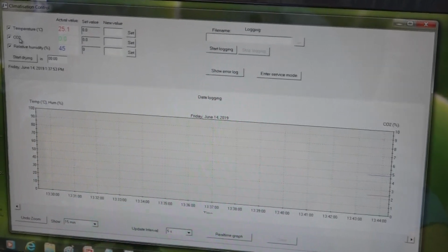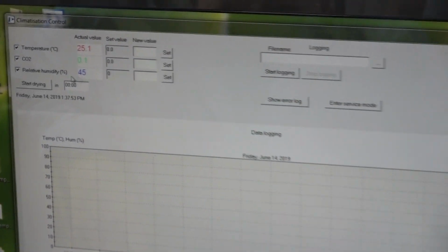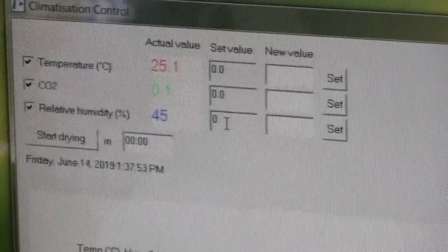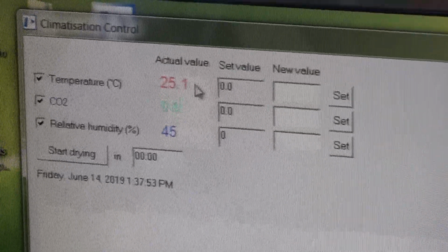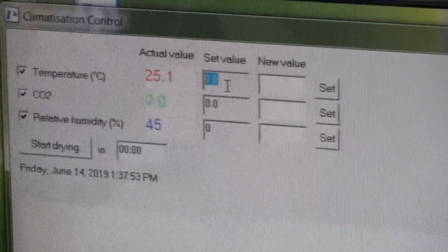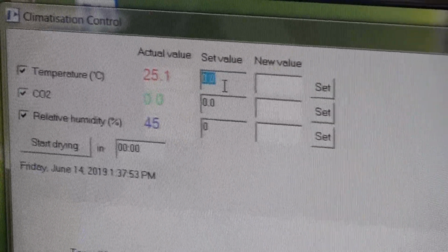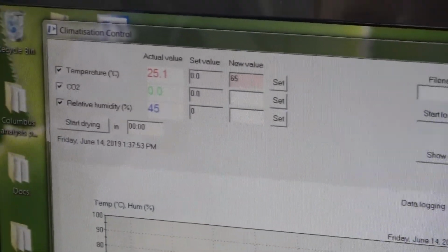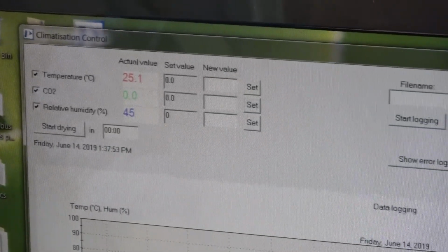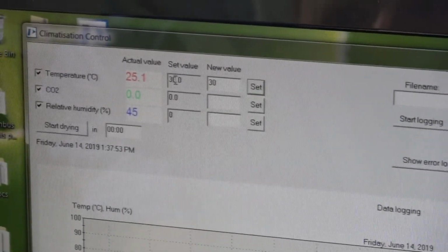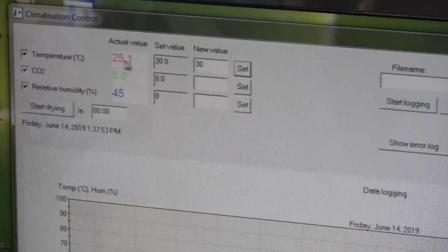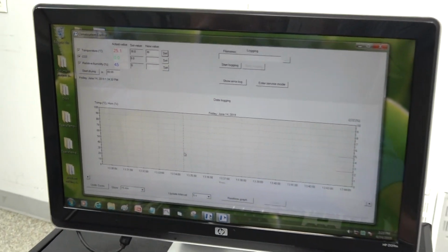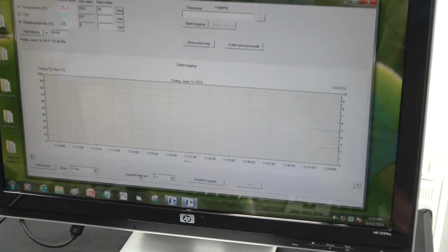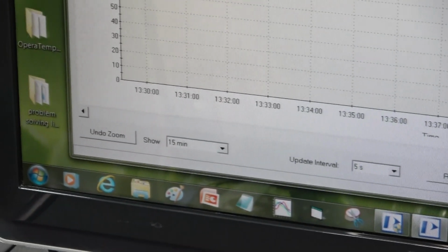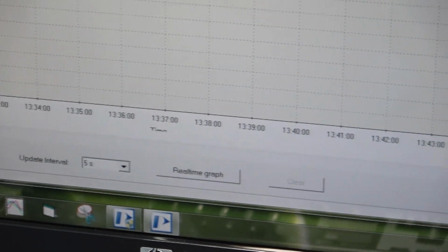So right now we are not connected to any CO2, so it's just registering 0. There's 45% relative humidity going on right now, so we can increase or decrease it through this window here, and then of course the temperature up here. So it's just a matter of entering in what you want. Say if I want to put in 65, which we definitely wouldn't want, but I'll put in 30 and hit set. So now the set value is 30, and this will just start slowly working its way up to that. So everything works great. I've tested everything. A few different things down here. You can update intervals and show every 15 minutes. So just a simple graph logging for the live cell imaging, but just a beautiful looking machine.